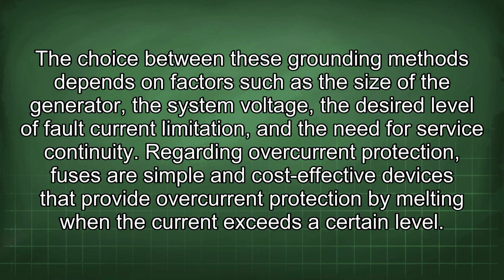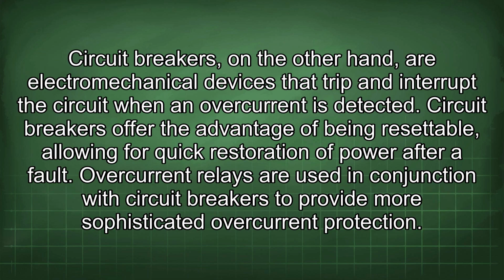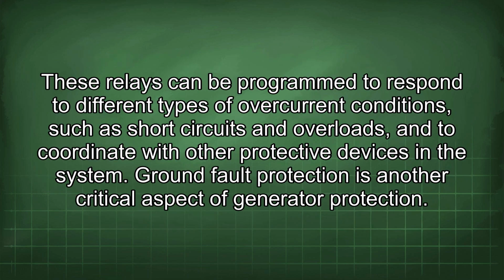Regarding overcurrent protection, fuses are simple and cost-effective devices that provide overcurrent protection by melting when the current exceeds a certain level. Circuit breakers, on the other hand, are electromechanical devices that trip and interrupt the circuit when an overcurrent is detected. Circuit breakers offer the advantage of being resettable, allowing for quick restoration of power after a fault. Overcurrent relays are used in conjunction with circuit breakers to provide more sophisticated overcurrent protection. These relays can be programmed to respond to different types of overcurrent conditions, such as short circuits and overloads, and to coordinate with other protective devices in the system.